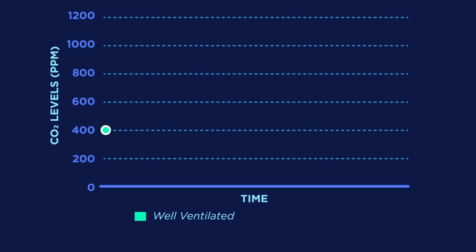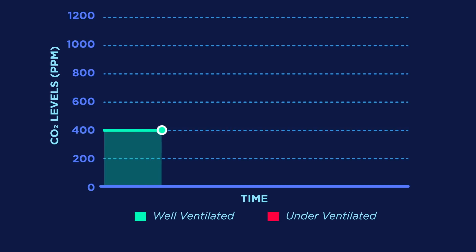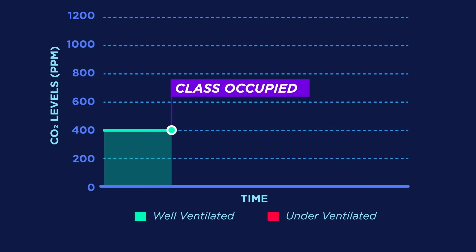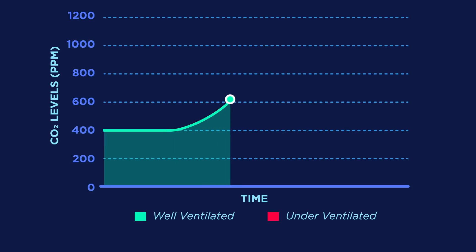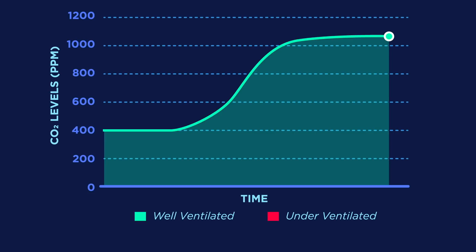Monitoring CO2 levels is a useful and convenient way to monitor ventilation. You can see here how CO2 concentrations change throughout the day in a classroom. When the classroom is empty at the beginning of the day, CO2 levels are about 400 parts per million, or ppm, which is the outdoor air concentration of CO2. When students come in, the level of CO2 will rise. In a well-ventilated classroom, it will level off below 1,100 ppm.